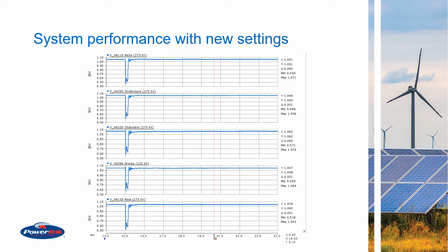So the key is, again, here we could have got the same response by increasing the fault level of the area. In other words, we could resolve this problem by adding more fault level in that area. However, the point that I want to highlight here is that if we tune the control system correctly, we can also improve the system strength. And the key to the success of control retuning is the partnership with the OEM, because our experience is that without this partnership with the OEM, these retunings are not possible.